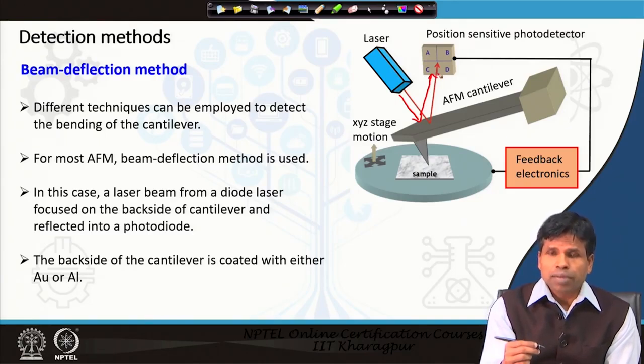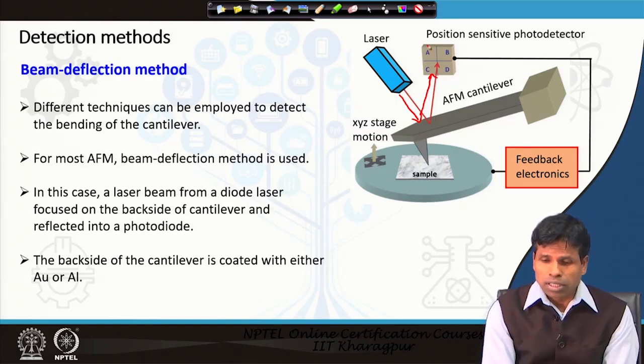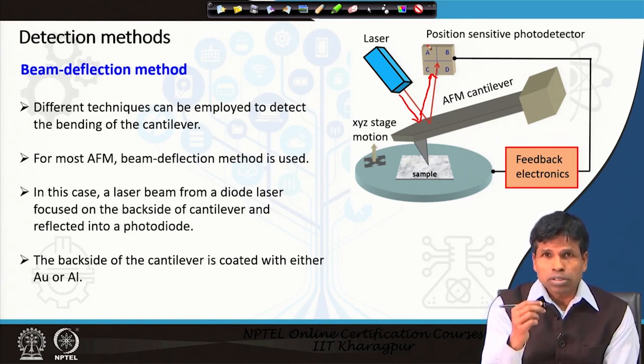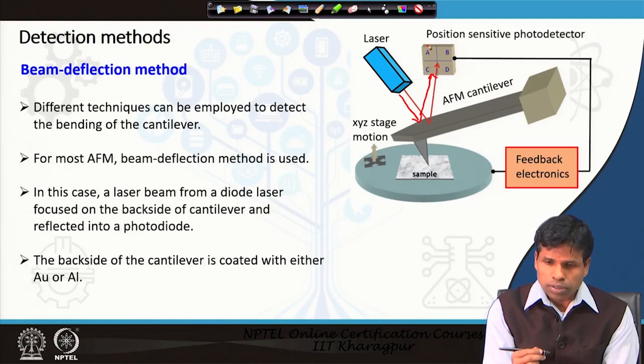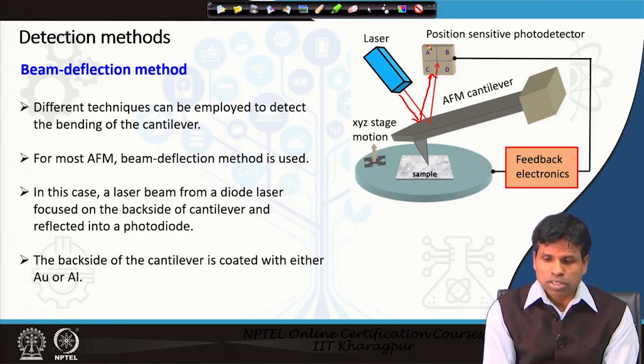As the cantilever goes up and down, the beam position will go up and down on the position-sensitive detector. With that, we can measure how much the cantilever is bending upward or downward, and thereby know the height or topography of the sample across the surface.